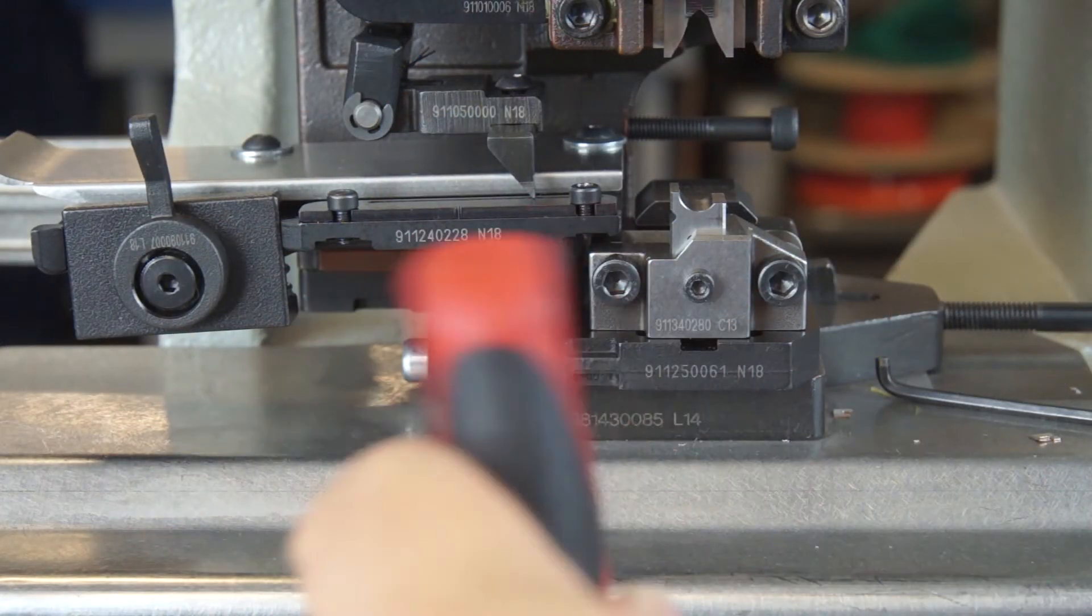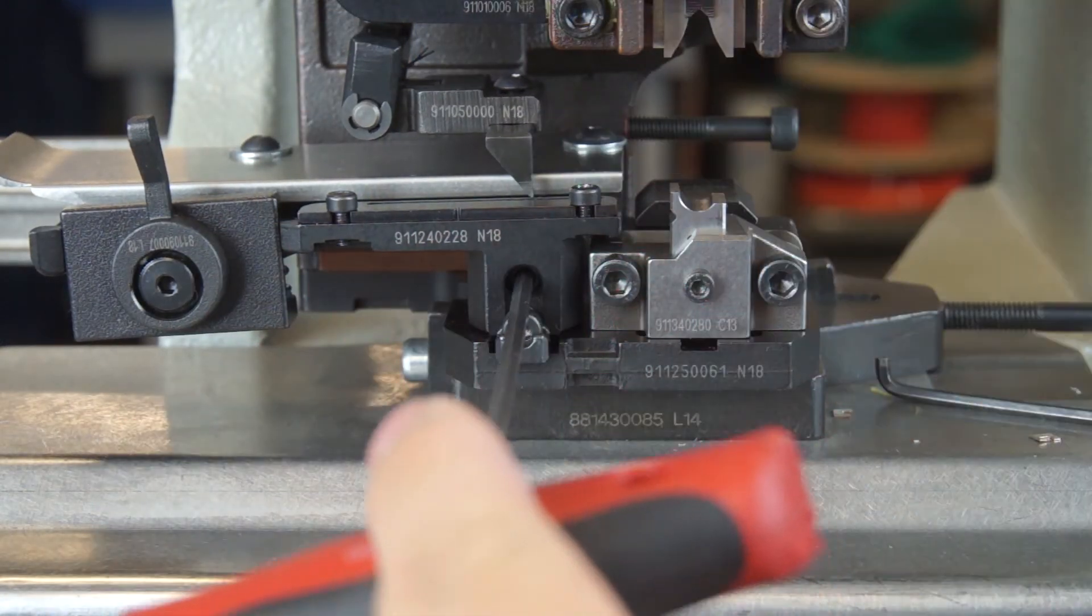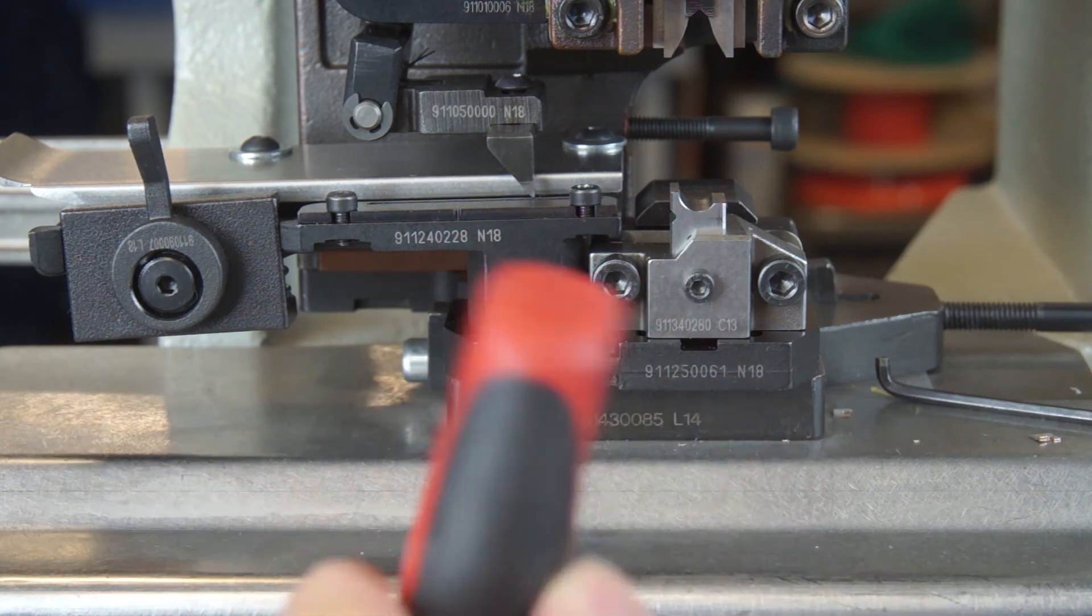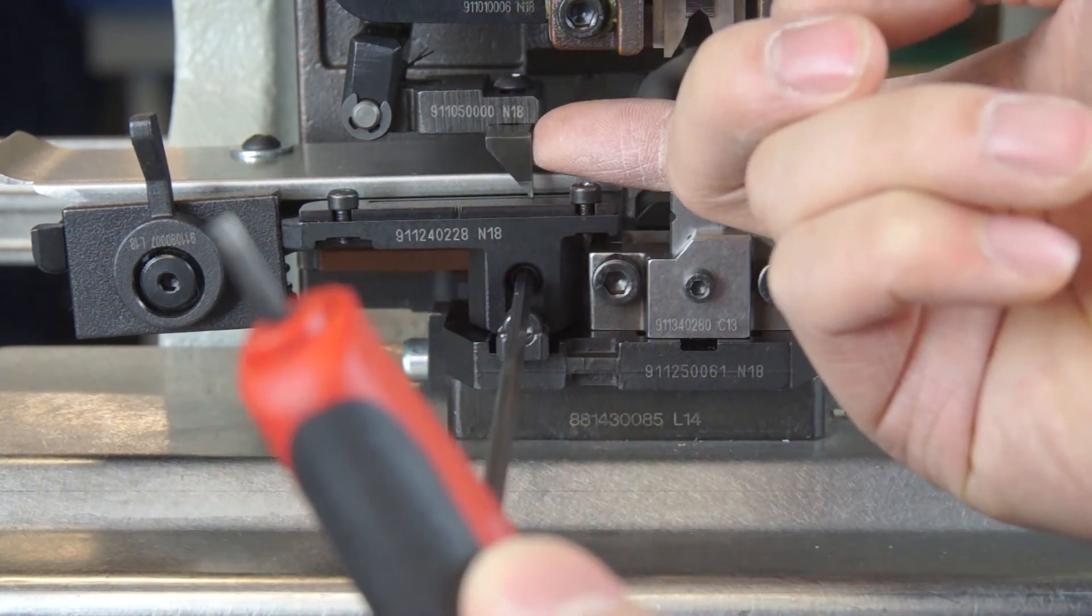To move the slide forward and back, take a 3mm hex wrench and turn the screw above the locking wedge. Turning the screw clockwise will move the slide closer to you, and turning it counterclockwise will move it further away.